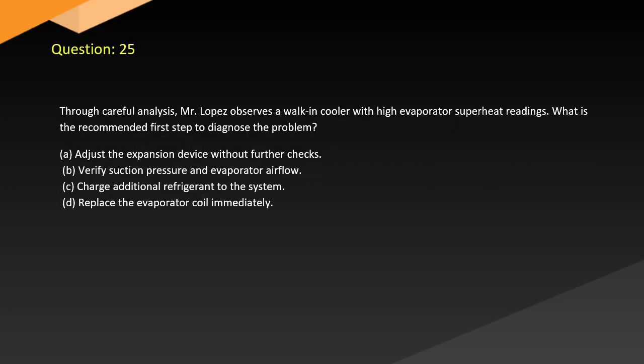Question 25. Through careful analysis, Mr. Lopez observes a walk-in cooler with high evaporator superheat readings. What is the recommended first step to diagnose the problem? A. Adjust the expansion device without further checks. B. Verify suction pressure and evaporator airflow. C. Charge additional refrigerant to the system. D. Replace the evaporator coil immediately.